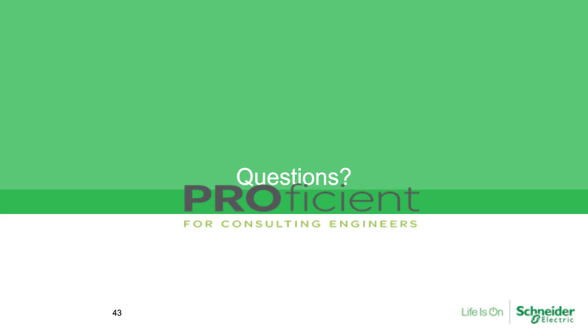Good to know. Phil, here's another question. What are the typical BIL ratings? So typical BIL ratings are 150 kV BIL, 170 kV BIL, and you do see it up to 200 kV BIL. A little bit of detail about this. There currently is not an IEEE standard for GIS. It's in draft form. It probably should be released in the next year or two. In fact, one of our Schneider engineers is chairing the committee, and we've all been very deeply involved on that standard.